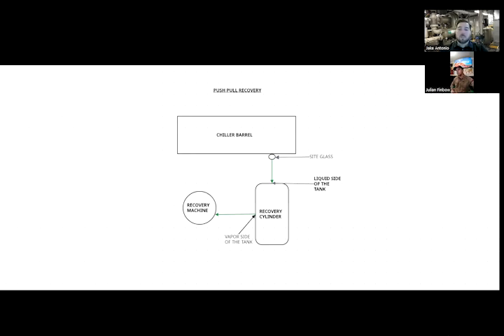So now what's happening is we're going to be pulling vapor off the top of the recovery cylinder, and we're going to use our recovery machine to move the vapor back into the chiller - so into the recovery machine from the top of the bottle from the vapor side, and then out of the recovery machine is going to go into our chiller.